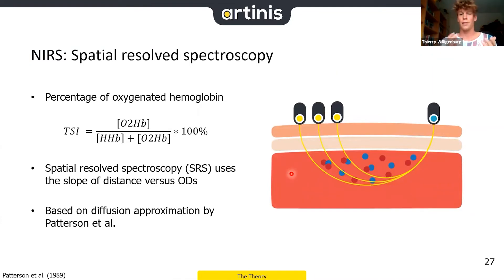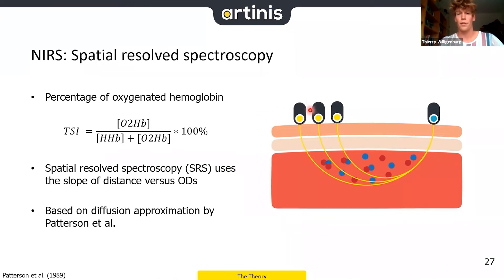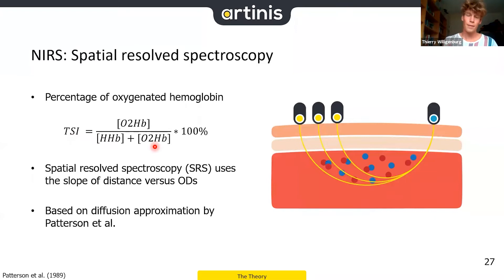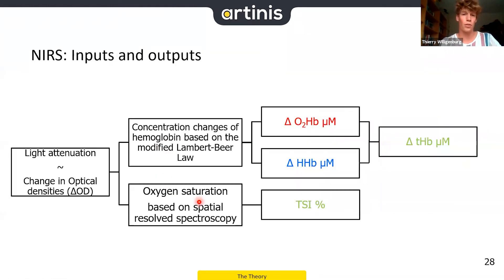Beside relative changes in oxy and deoxy values, we can also quantify an absolute value: the TSI, the tissue saturation index. It's based on spatial resolved spectroscopy, using the slope of distance versus optical density, based on the diffusion approximation by Patterson et al. TSI = oxyhemoglobin / (oxyhemoglobin + deoxyhemoglobin) × 100%, giving a percentage of oxygen in the tissue — an absolute value.